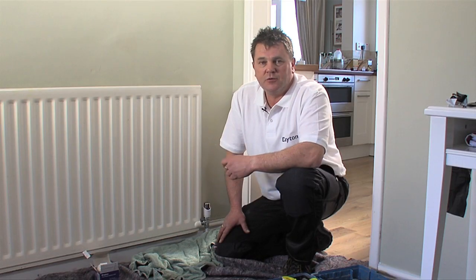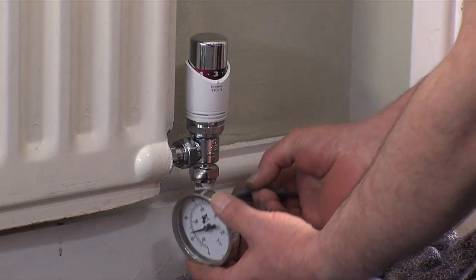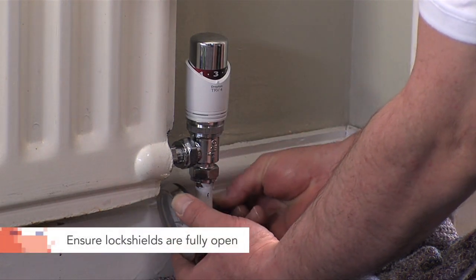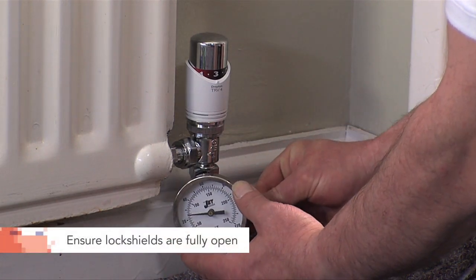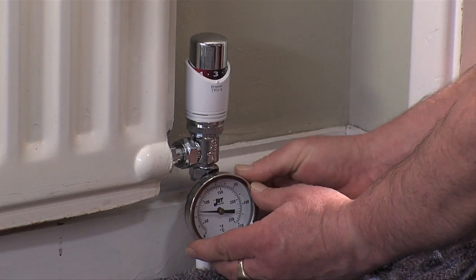First of all we've refilled the system — it's full of water. Now make sure the pump and boiler are turned on. Making sure that the lock shields are fully open, start at the radiator closest to the pump, checking the temperature of the flow and return pipes using clip-on thermometers.